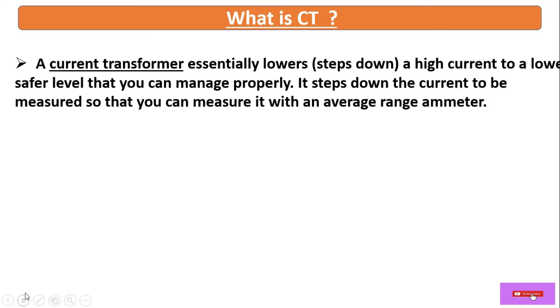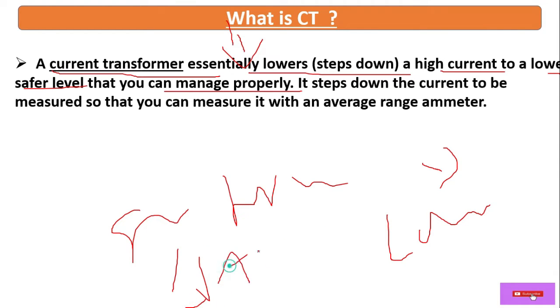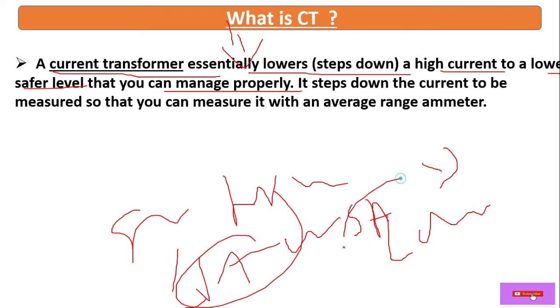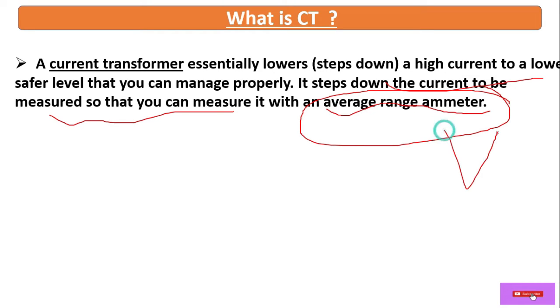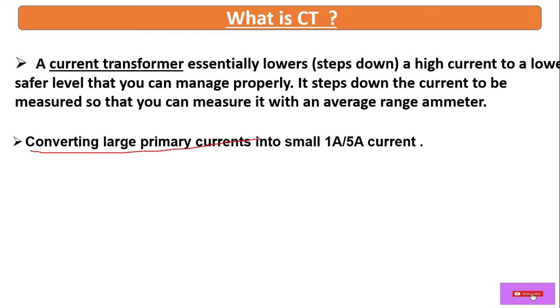So what is CT? CT stands for Current Transformer. A current transformer essentially lowers or steps down a high current to a lower, safer level that you can manage properly. Its function is to step down higher currents to a lower range — up to one ampere or five ampere. This is the ratio of CT on the secondary side, stepping down the current so that you can measure it with an average range meter.